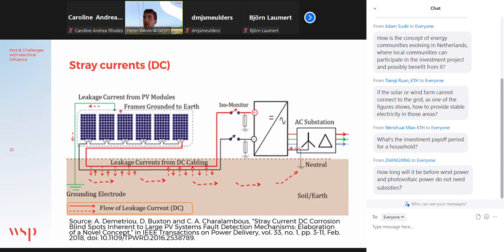It is limited by the protection systems that are inside the inverters in the PV system. There should be a device that measures the resistance between the DC cables and the ground. And if this resistance becomes too low, there is an electrical leakage, and the inverter will shut off, and the owner of the plant will come very quickly to repair that damage, because if the inverter is shut off, they lose income. And there is another measuring device that is monitoring the difference between the current going into the PV string and the current coming out. And if this difference is too big, then also the inverter will shut off.